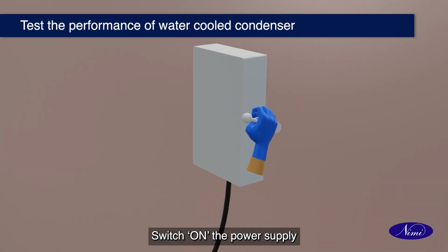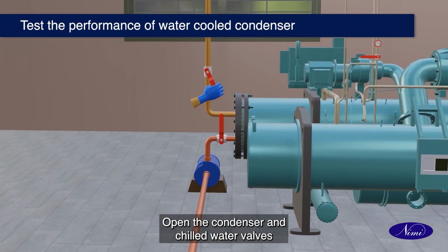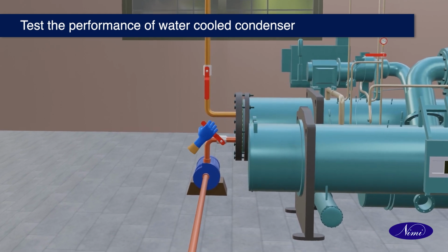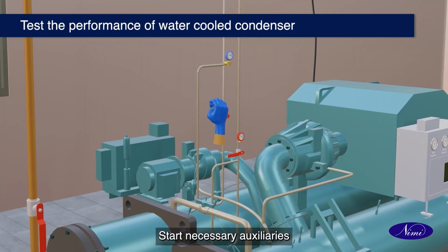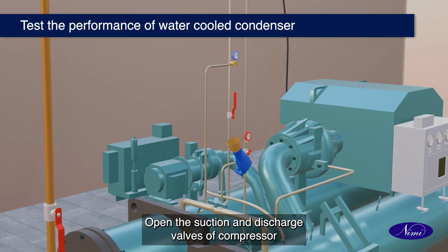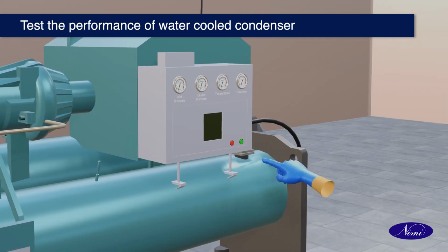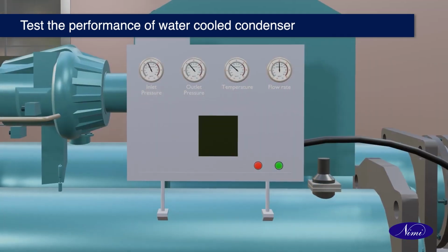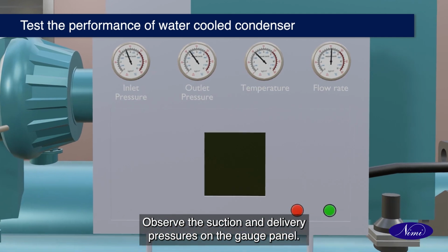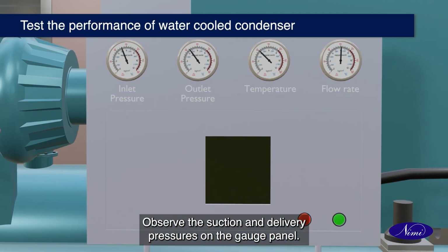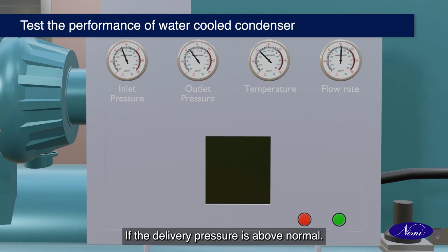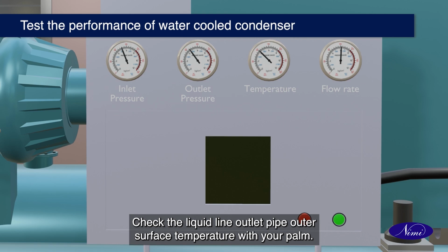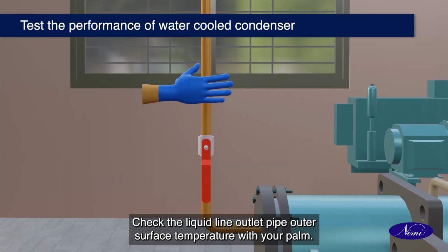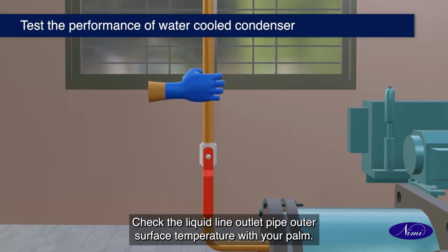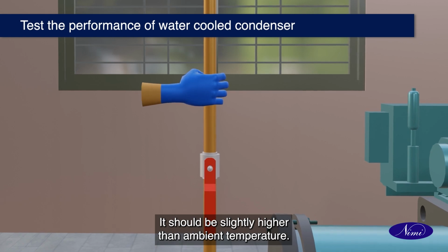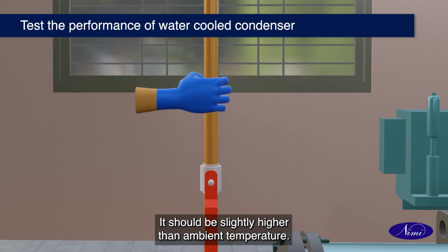Switch on the power supply. Open the condenser and chilled water valves. Start necessary auxiliaries. Open the suction and discharge valves of compressor. Start the compressor. Observe the suction and delivery pressures on the gauge panel. If the delivery pressure is above normal, check the liquid line outlet pipe outer surface temperature with your palm. It should be slightly higher than the ambient temperature.